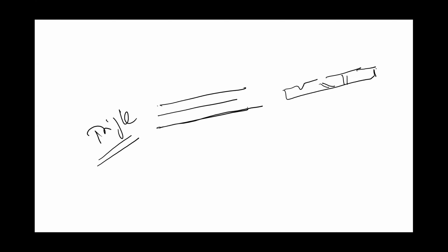Both are used in CSSD, but triple bar sealing is considered a better method because the breakage here is lesser than the solid bar seals. With solid bar seals, it may happen that at times there is a breakage, like this. In triple bar sealing, there should be one seal which is complete without any break. That is the rule that has been followed. If you have three seals, then at least one row should be complete without any break.